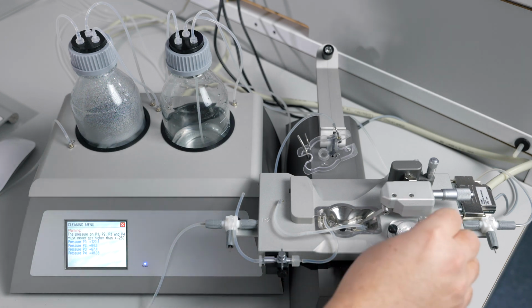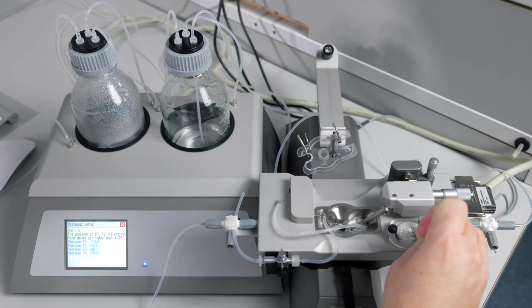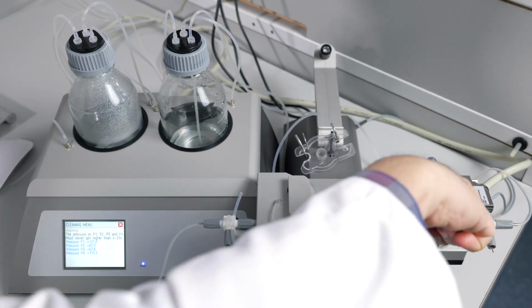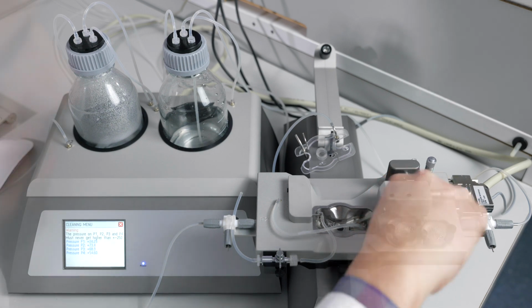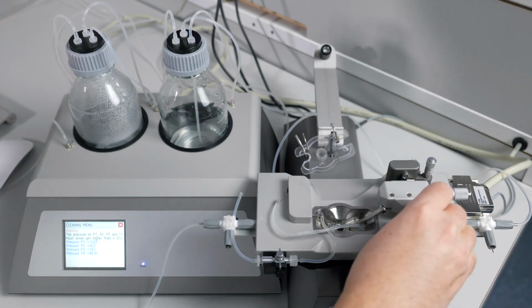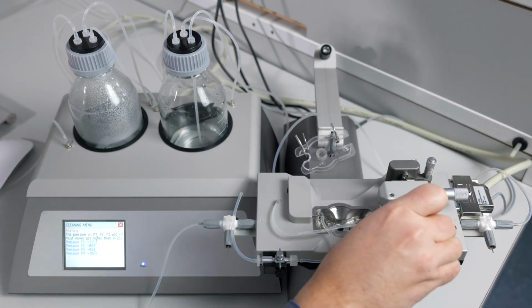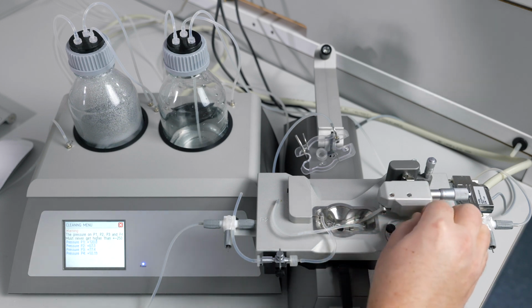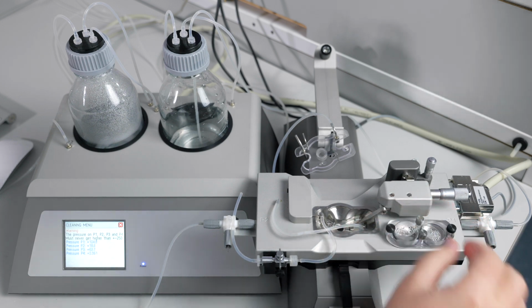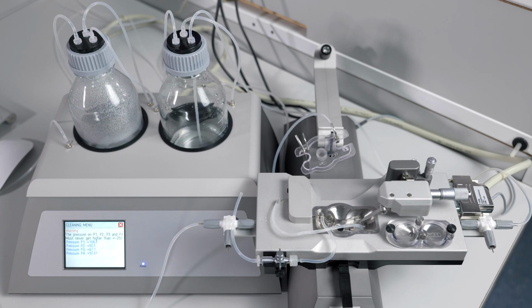While doing so, open the P1 release valve on the pulsation well. You can see this fill with water, and then close this, and repeat the same with P2. You will let this program run with distilled water for 10 minutes. After that, you can turn off pressure, empty the P1 and P2 bottles, retighten the caps, and let it run with air. This will empty all of the lines of the chamber.